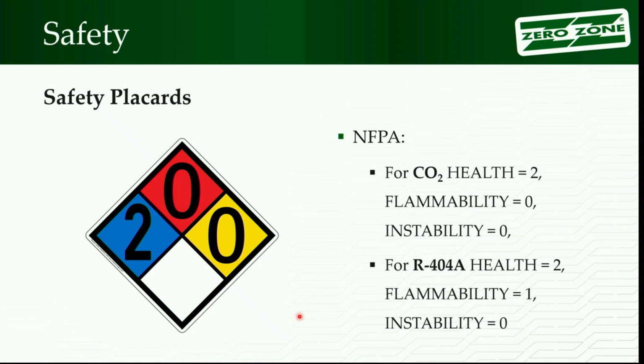Safety placards, so if you've got some CO2, you wind up with a 2 in health just because it's an asphyxiant. You wind up with the same thing, though, if you have 404, again, it's an asphyxiant, you wind up with a 2. 404 gets a 1 for flammability. 404 can burn, but the flame won't spread. So if you try hard enough, you can get 404 lit up, but it doesn't spread, so it's not considered, I guess, a flammable gas in the refrigeration world, but from a DOT standpoint, it has some flammability to it.